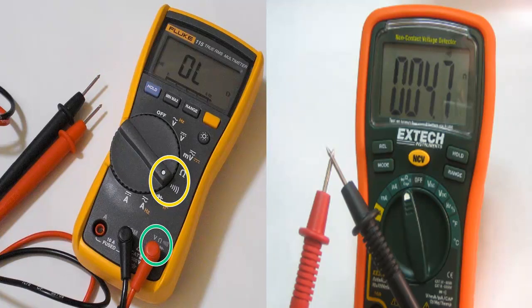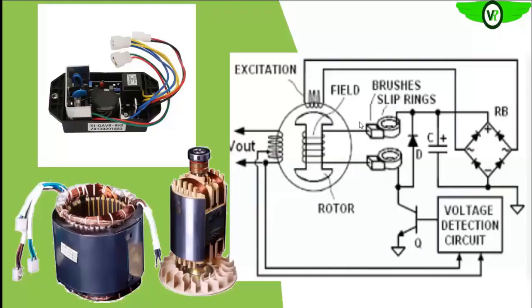So you see that the AVR is also a very important unit in the single phase generator. So how do you use the digital multimeter to test this? Remember, we have said that in testing this, you test for the continuity of each of the windings. You can test for the resistances, okay? And then test if it is short to ground or not. Those are the three tests that you can carry out when the equipment is dead. But when it is live, okay, you test the output to ascertain that what is coming out is what is desired. Okay, so those are what you can do live.